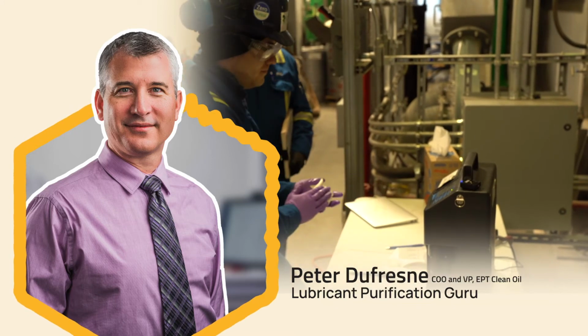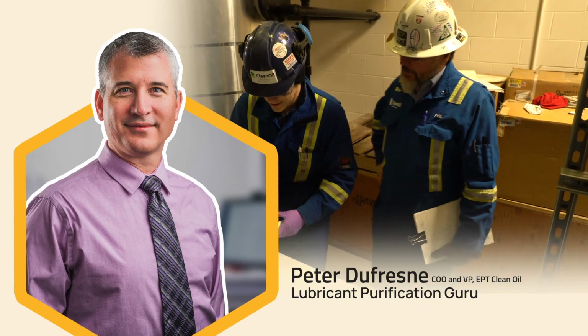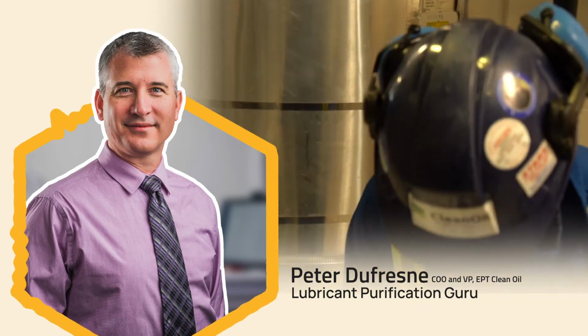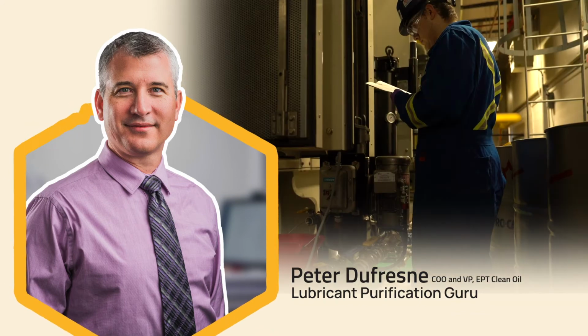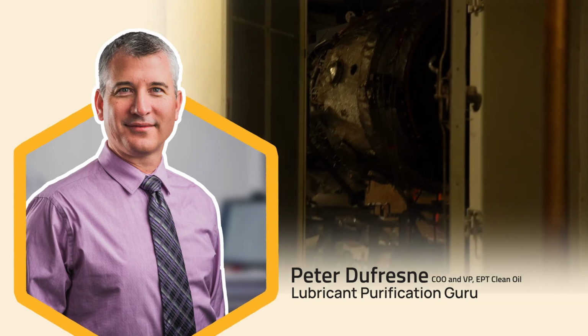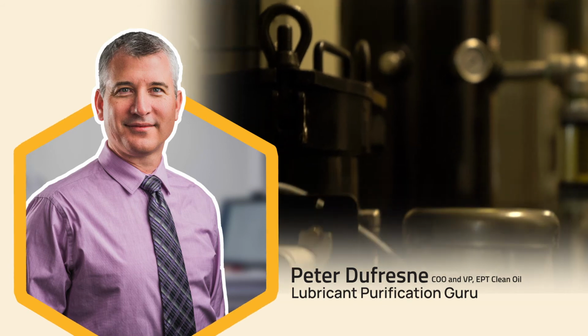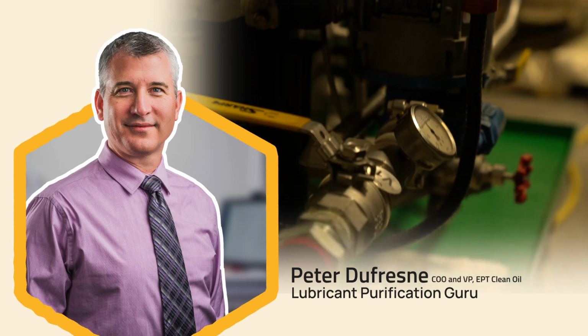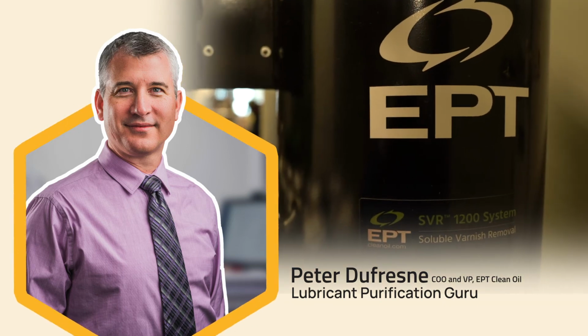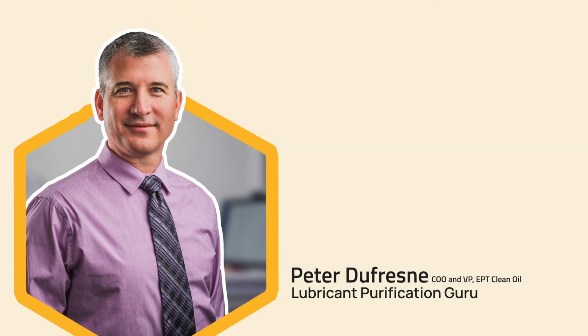Ideally, what you want is for the users of that gas turbine to understand implicitly that, I'm losing 10% of my additive per year. I'm on track for a 10-year oil life, right? Or I'm depleting my additives at a rate of 30% per year, so I'm on track for a 3-year life. Just the recognition of this and the adjustment of the maintenance strategy to deal with that scenario, so you can actually align your maintenance windows with your oil changeout intervals, right? And then in that case, you're also able to maximize your production.